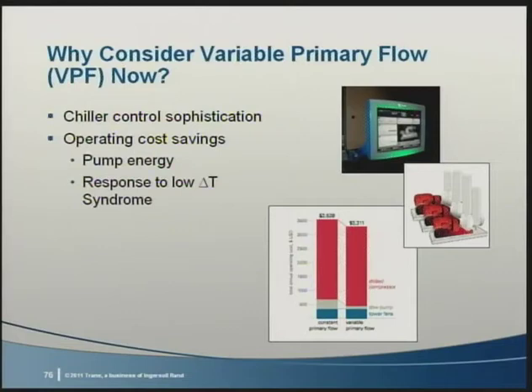Retrofit opportunities are primarily to reduce pump energy use or to respond to system issues, such as the so-called low delta T syndrome. Low delta T occurs when coils selected to provide a specific temperature difference return water at a lower delta T. This could occur because the coils are dirty, airflow is not correct, controls are being performed improperly, or even because the coils have 3-way valves. Mick, why don't you walk us through several retrofit scenarios?